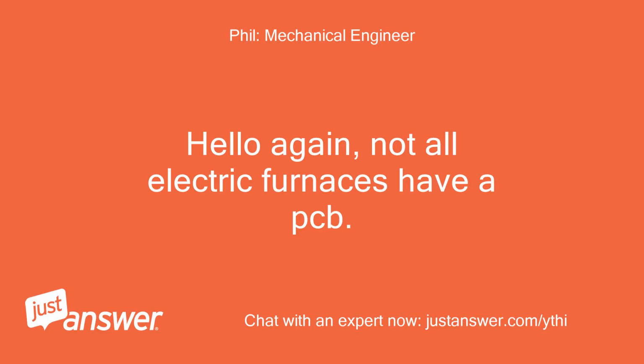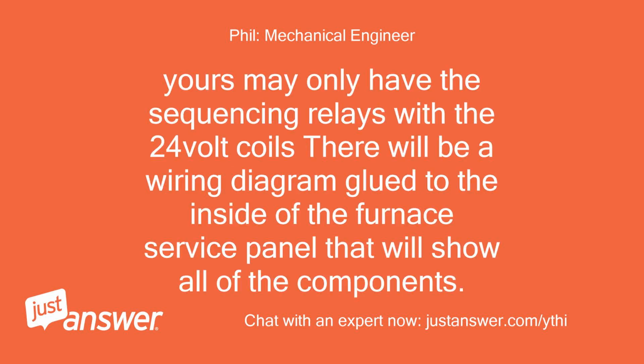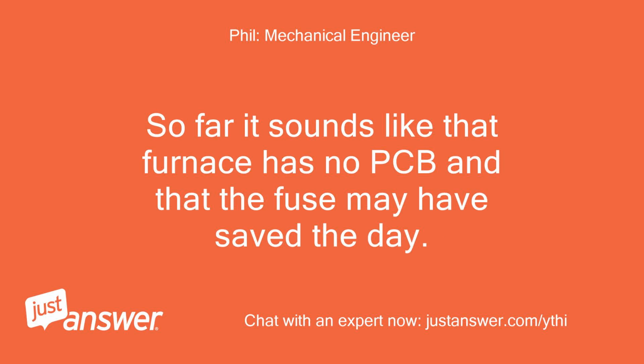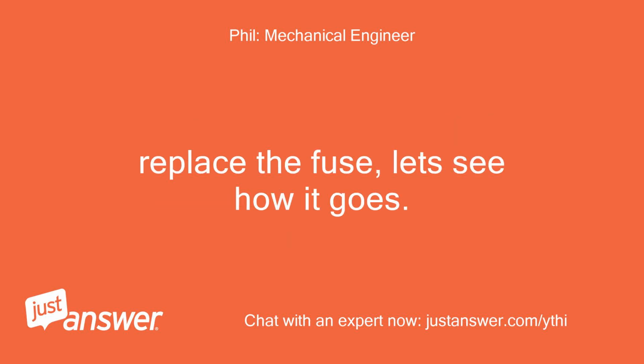Hello again. Not all electric furnaces have a PCB. Yours may only have the sequencing relays with the 24-volt coils. There will be a wiring diagram glued to the inside of the furnace service panel that will show all of the components. So far it sounds like that furnace has no PCB and that the fuse may have saved the day. Replace the fuse. Let's see how it goes.